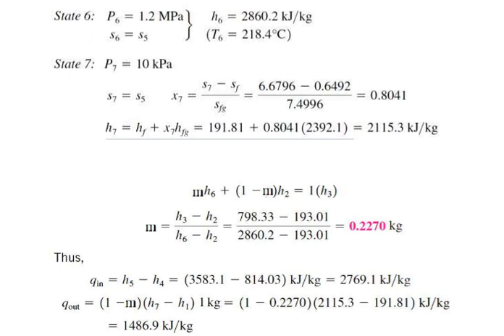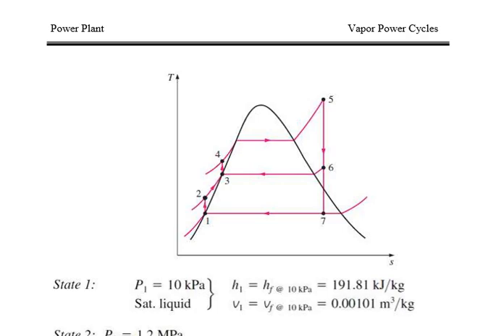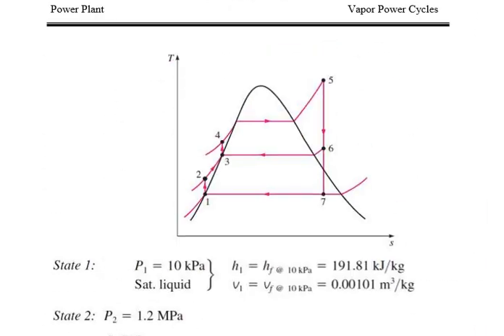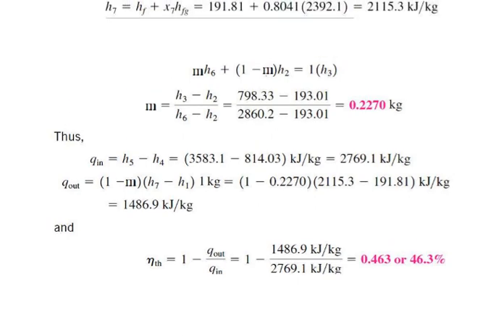After studying both open and closed feed water heaters, we compare their advantages and disadvantages. Open feed water heater: simple and inexpensive. Closed feed water heater: complex and expensive due to the internal tubing network. In terms of heat transfer, the open feed water heater is more efficient due to direct contact, whereas the closed feed water heater is less efficient since the two streams are not in direct contact.